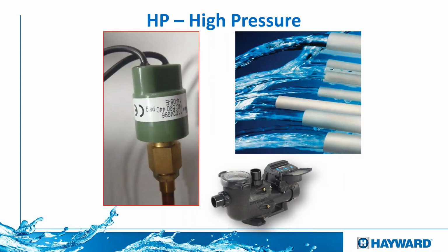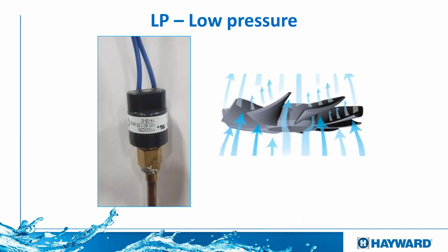If you get the code HP, which means high pressure, again, the most common issue with this is lack of flow. So before you start taking refrigerant out of the heat pump, if you have no gauges, I will definitely check the water flow. If we have only a little bit of flow going through the heater, the refrigerant will overheat. The pressure will go way higher because there's not enough water cooling down the refrigerant, and that will give you that code. So we need to put more water through the heat pump.